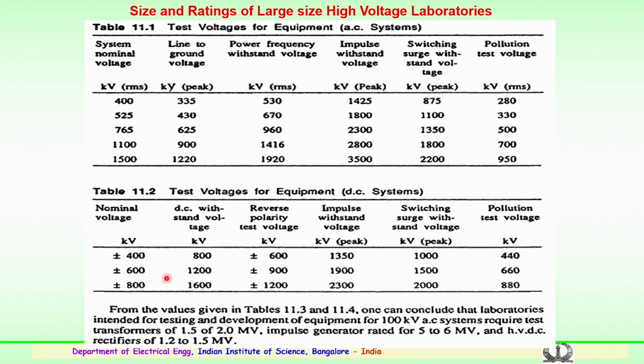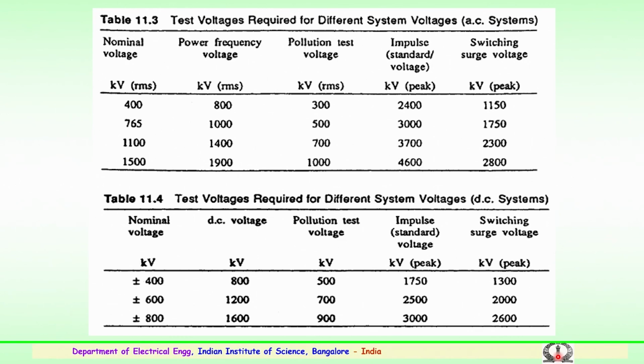Similarly for plus minus 600 kV these are the values. 1200 is the withstand voltage, the reverse polarity voltage being plus minus 900 kilovolts, the lightning impulse is 1900 kilovolts, the switching surge withstand voltage is 1500, and the pollution test voltage is 660 kV. And for 800 kV HVDC systems, the DC withstand voltage is 1600 kilovolts, the reverse polarity test voltage being 1200 kV, the lightning impulse voltage is 2300 kV, the switching surge withstand voltage being 2000, and the contamination or pollution test voltage being 880 kilovolts. Very important, these are all as per the standards which have been specified both nationally and internationally. So, this gives the test voltages required for different system voltages for AC and DC.